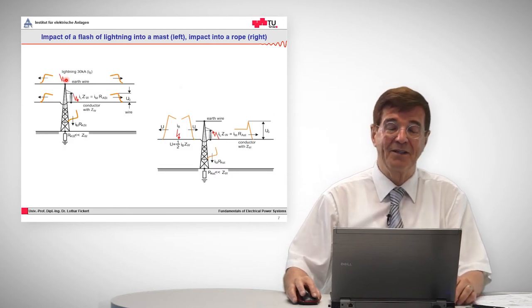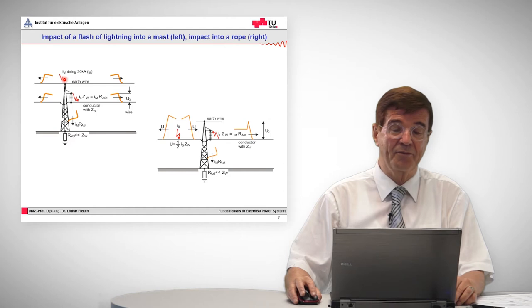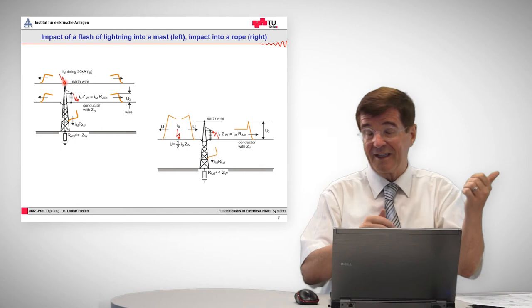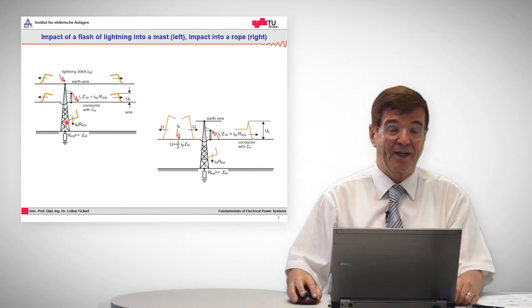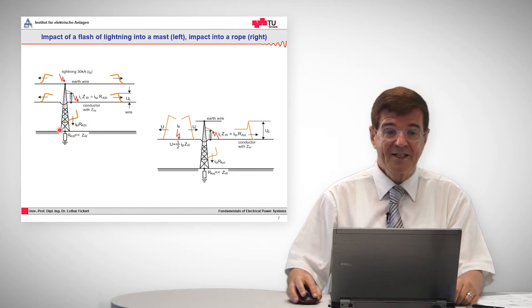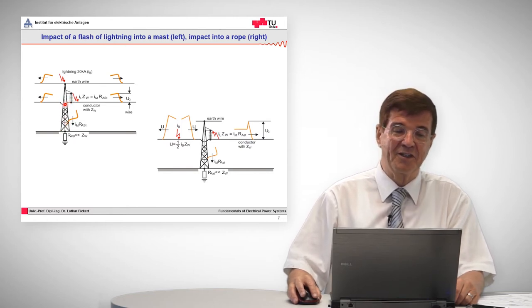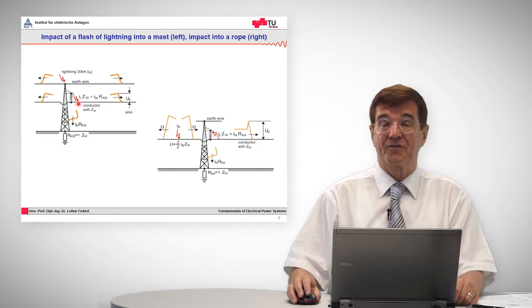For example, if there's a flash of lightning of 30 kilo amps that goes straight into the tip of such an overhead pole, the current is divided into three parts: one goes to one side, one to the other side, and the third goes down through the pylon. If this pylon has a bad or high grounding resistance, we have a built-up of voltage which is called a reverse voltage, and that may cause a spark over from this now energized steel pylon into the live wire. That is called the reverse flash over.